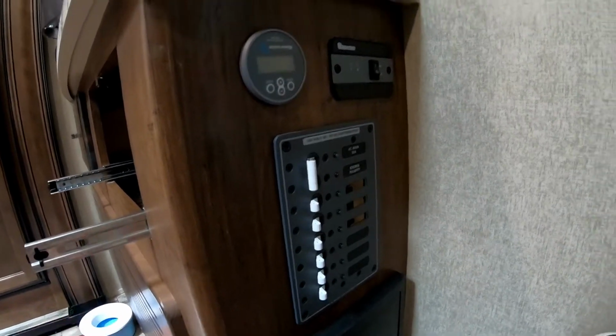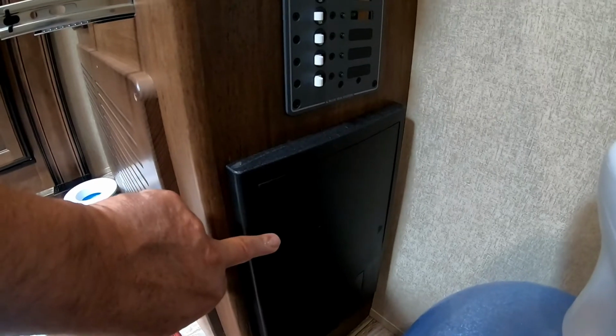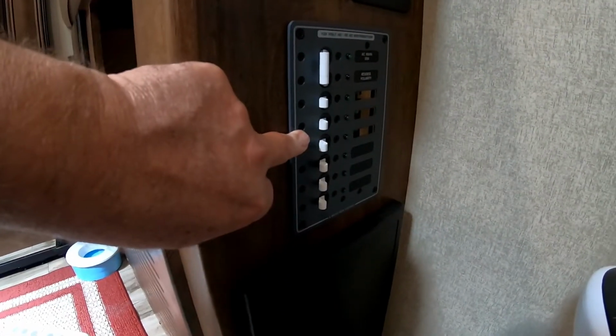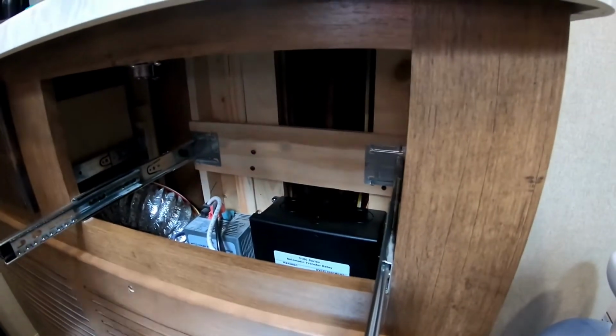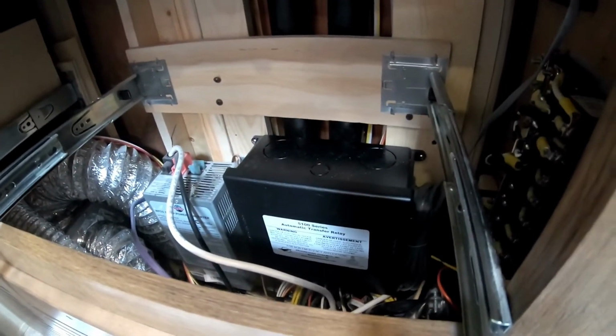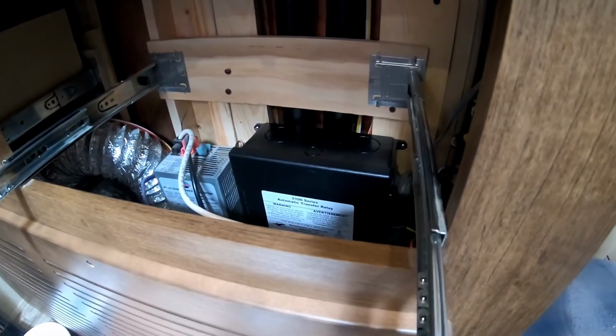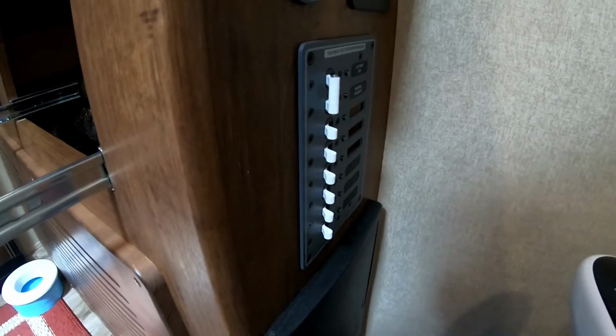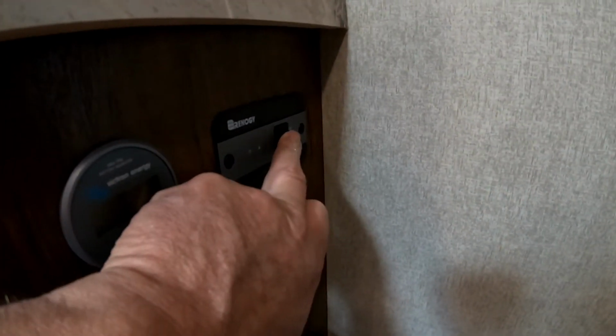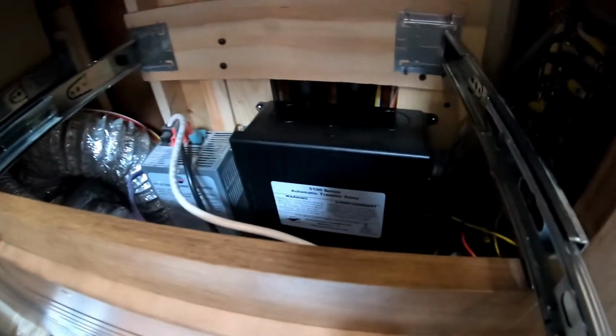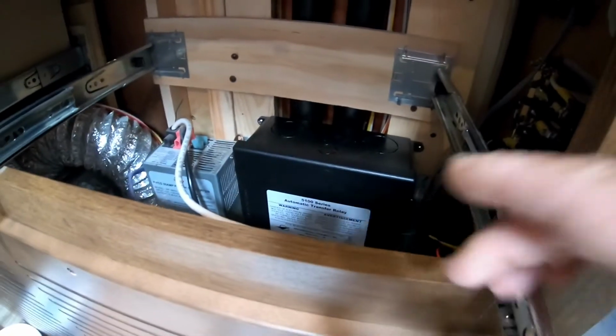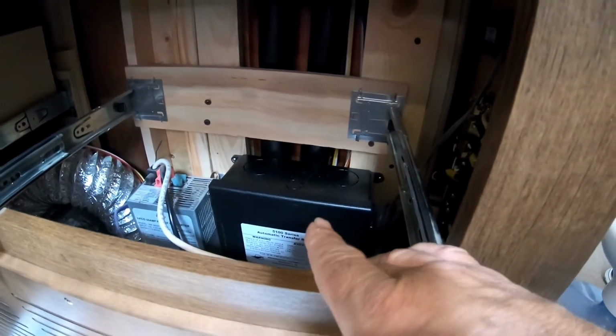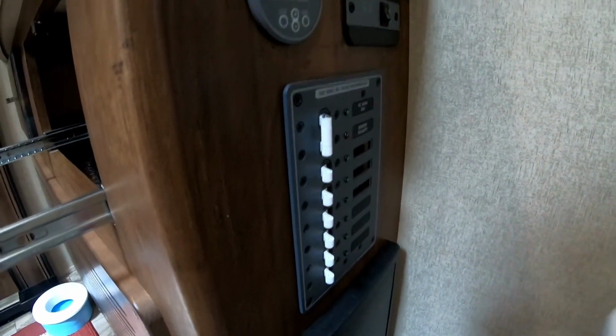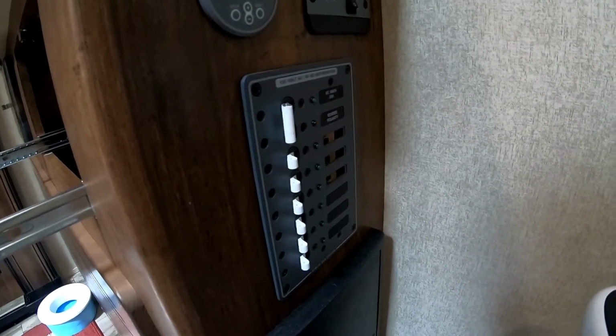We're going to rewire the receptacles out of this panel up to this panel. How will that work? One of the breakers in here will go to that auto switch. When it sees power from the auto switch, it will automatically maintain power from the pedestal or generator through the power switch to the receptacles. If we lose power and I have my inverter on, the power will switch over to alternate power, which is the inverter. It will go through the auto switch but only power this auxiliary panel, which is limited to 30 amps, the rating of the panel.